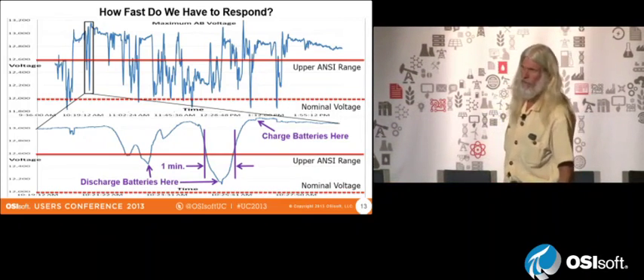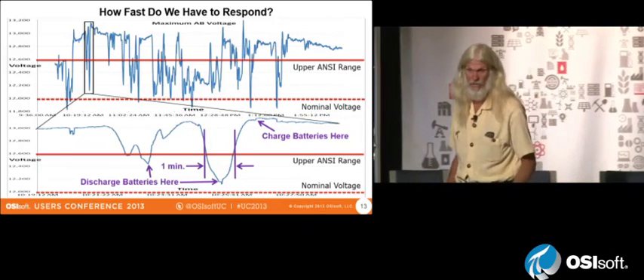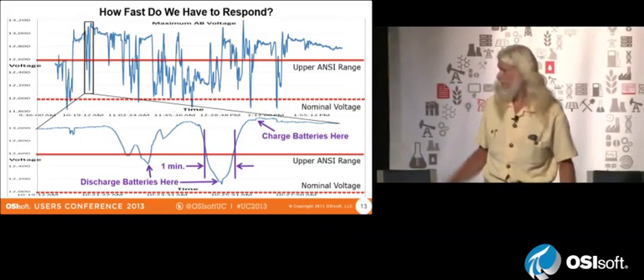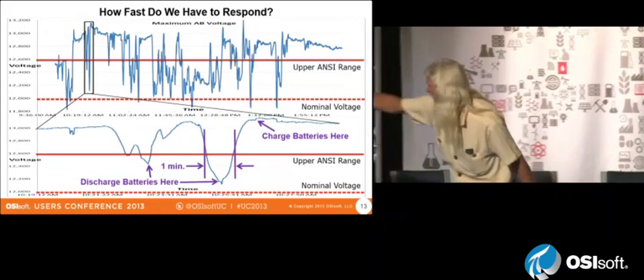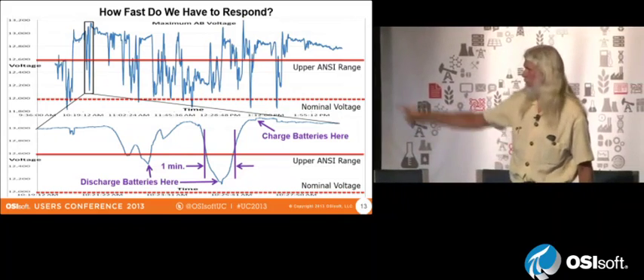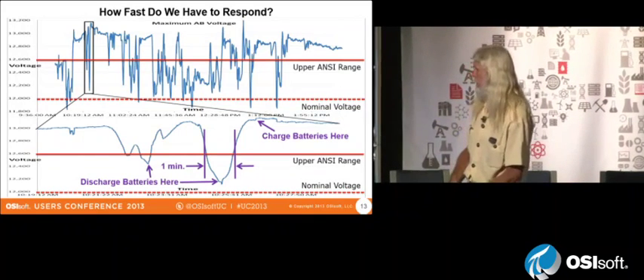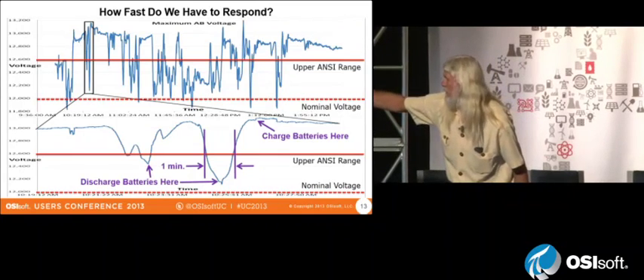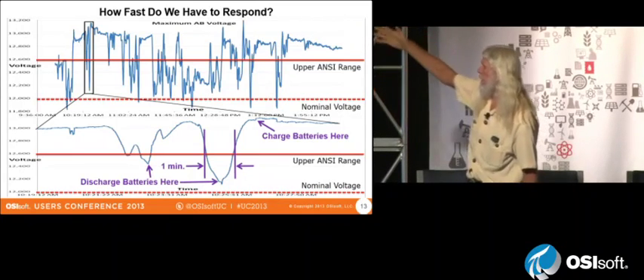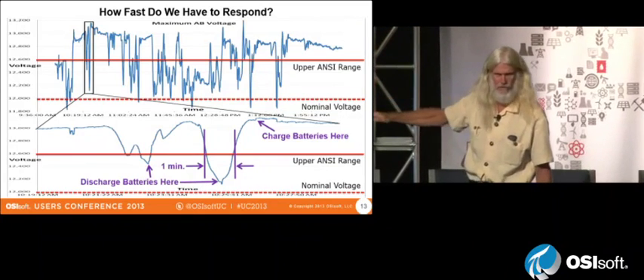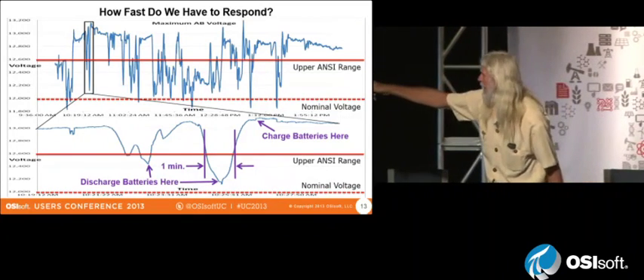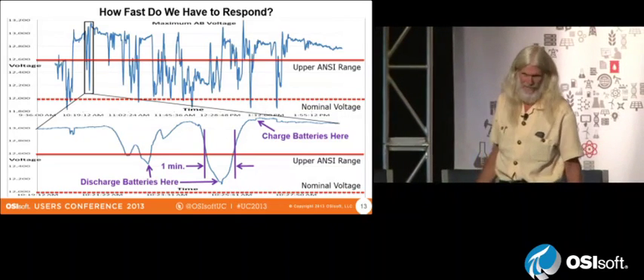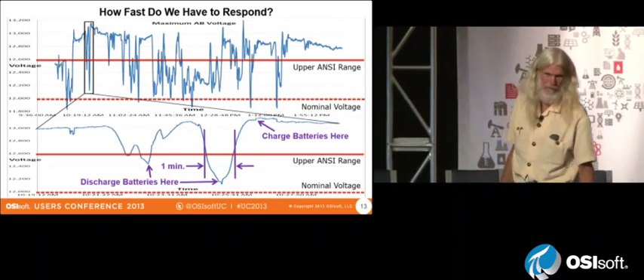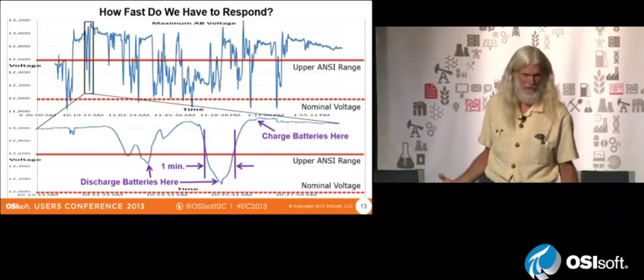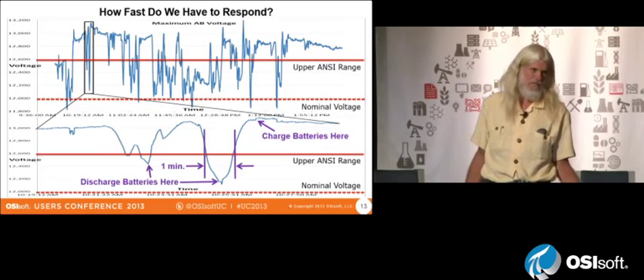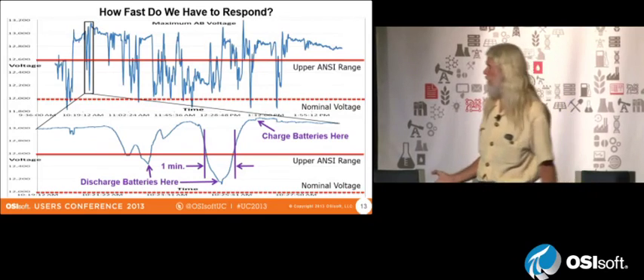Now, the typical solution being implemented today is to spend high amounts of money on peaker plants to deal with this issue. A peaker plant takes that entire graph just to turn on, it can't even come close to keeping up. Whereas the equipment we do can actually charge the batteries when the voltages are going up and discharge them when it's going down. So the actual amount of time it's doing this battery balancing is only a couple minutes at a time, meaning the amp hours or kilowatt hours you're actually taking in and out of the batteries becomes insignificant. In fact, you could actually do it with ultracapacitors.